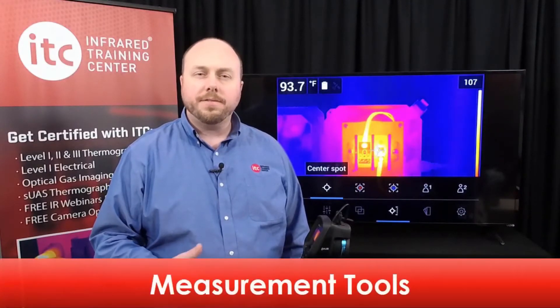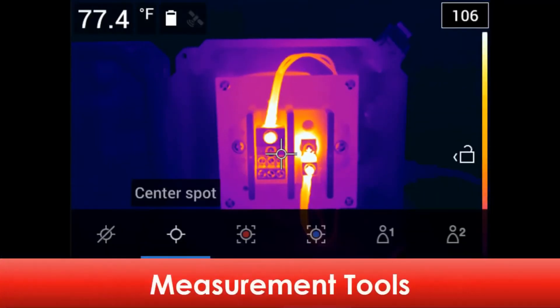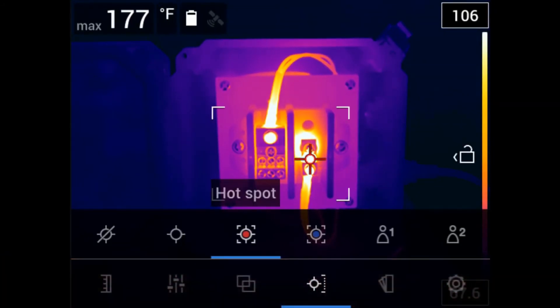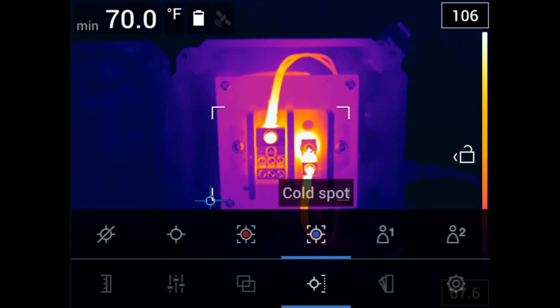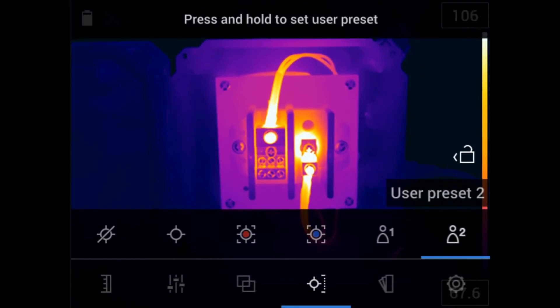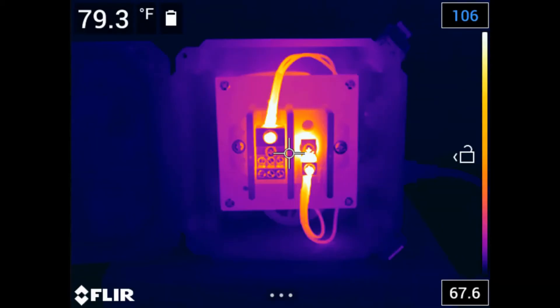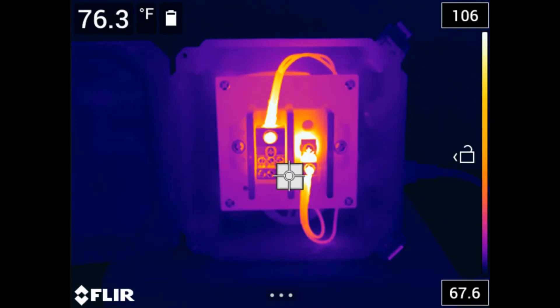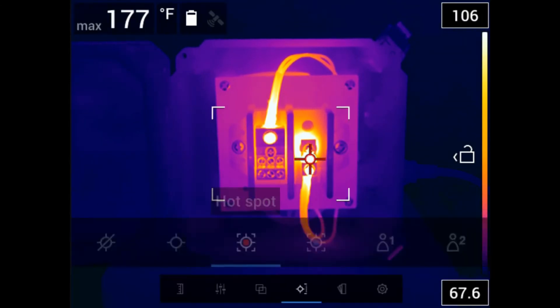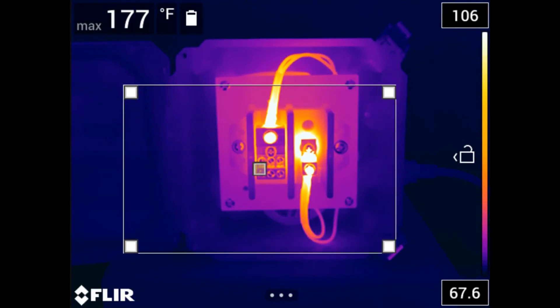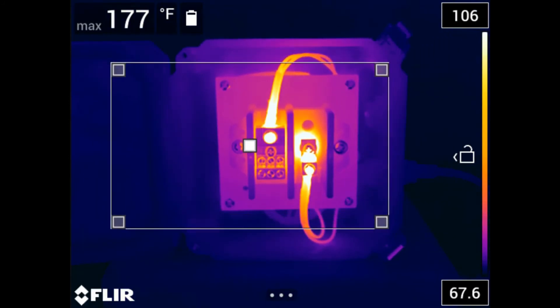This thermal imager also offers several kinds of temperature measurement tools. These include a center spot meter; a hot spot box, which provides the maximum temperature inside the displayed box; a cold temperature box with the minimum temperature value displayed; and two user preset options. Selecting the center spot displays the apparent temperature value in the upper left-hand corner of your display screen. You can move the spot around the image by simply dragging it with your finger, same with the hot and cold spot area boxes. You can also adjust the size and location of the box by dragging the corners outward, or by touching the center of the box and moving it around the screen.